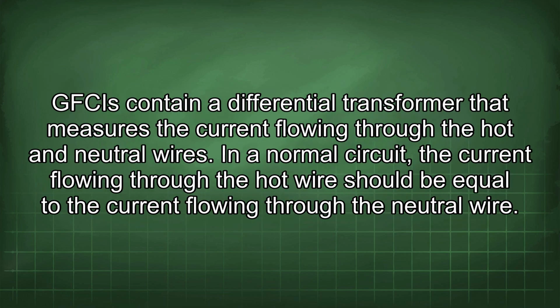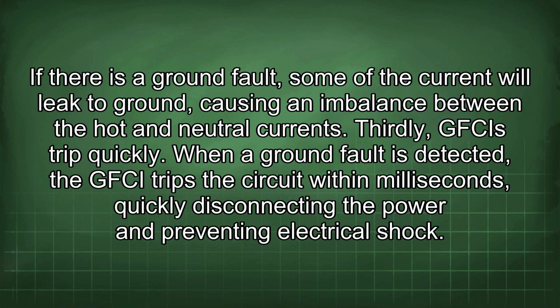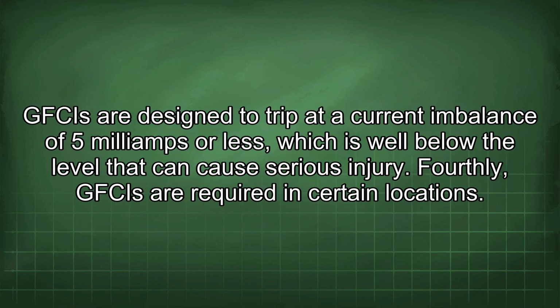Secondly, GFCIs work by measuring current balance. GFCIs contain a differential transformer that measures the current flowing through the hot and neutral wires. In a normal circuit, the current flowing through the hot wire should be equal to the current flowing through the neutral wire. If there is a ground fault, some of the current will leak to ground, causing an imbalance between the hot and neutral currents. Thirdly, GFCIs trip quickly. When a ground fault is detected, the GFCI trips the circuit within milliseconds, quickly disconnecting the power and preventing electrical shock. GFCIs are designed to trip at a current imbalance of 5 mA or less, which is well below the level that can cause serious injury.